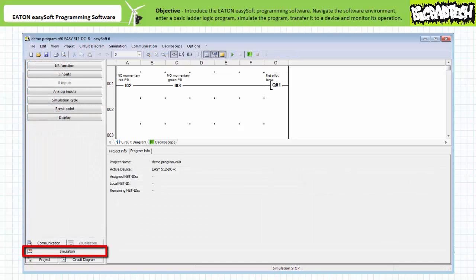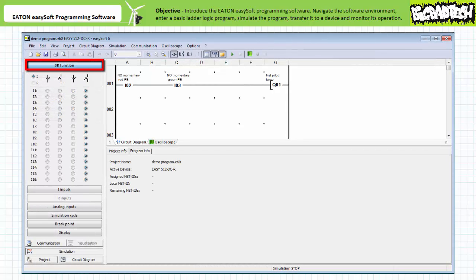The simulation window allows a means of testing and verifying the functionality of a program before going live with real hardware in a production environment. The simulation workspace shows the status of the program inputs and outputs as dictated by simulated field input conditions. Before pressing play, open the IR functions on the left menu to modify the electromechanical nature of the simulated field input devices. This utility is the reason why I have a special fondness for the Eaton easySoft programming software. A lot of the freely available demo software does not allow a user to modify the electromechanical nature of the simulated field input devices and often restricts a user to normally open devices.